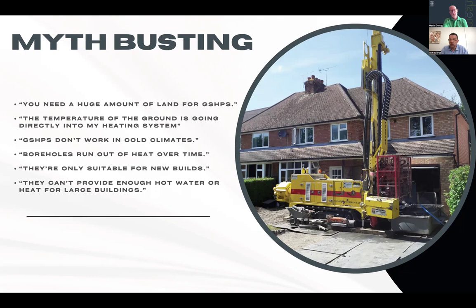But the other thing was, people are thinking that the heat that's coming from the boreholes is actually going into their house. And they say, okay, the ground is like 13, 14 degrees. How is it going to warm up the house? That's not the case. We are using the heat to provide the energy to the heat pump, which is then extracted, and then it's boosted to 45 for central heating or 50 for your hot water. So that's some of the questions our clients ask, how does it work? And we're not drilling 1 mile down into the core where we could generate 70 or something like that. You're only going to see 10, 11 degrees, but that's just a kind of educational thing that people don't understand.